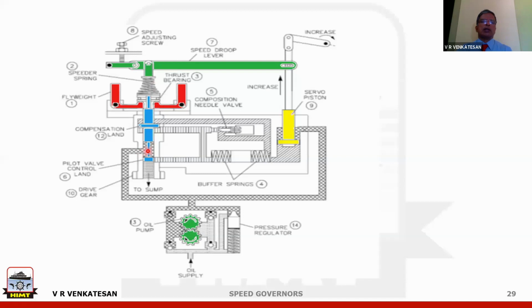But in this case, the same hydraulic oil is used for moving the pilot valve. Another way, it is like you are telling the governor that the engine speed is already increasing. Because the pilot valve will move upwards again, the fuel going to the engine will be controlled. So this is called negative feedback. Negative feedback always means the gain is reduced. Normally you use negative feedback in systems where the gain is too high already.